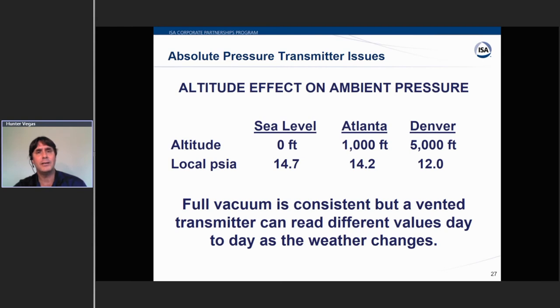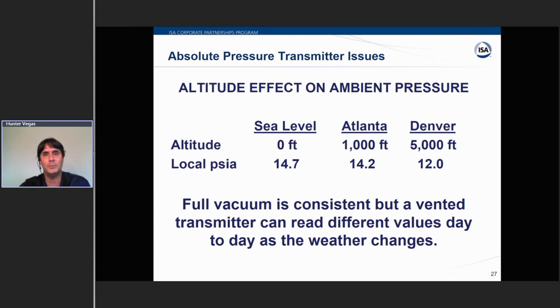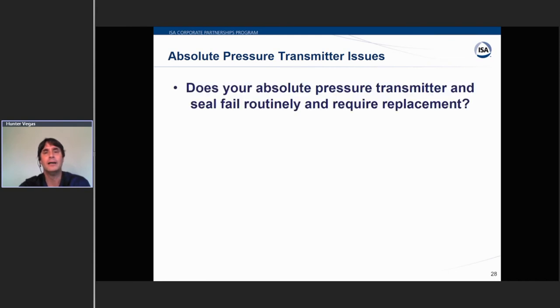For absolute pressure transmitters: a full vacuum is a full vacuum everywhere in the world — that's straightforward. It's the vented side, zero PSIG, that drifts and changes by location. At sea level, 14.7 PSIA is ambient; in Atlanta it's 14.2; in Denver it's about 12. It also moves with the weather — if you calibrate it flawlessly today and a cold front comes through, the reading can drift because vented today is not the same as vented yesterday.